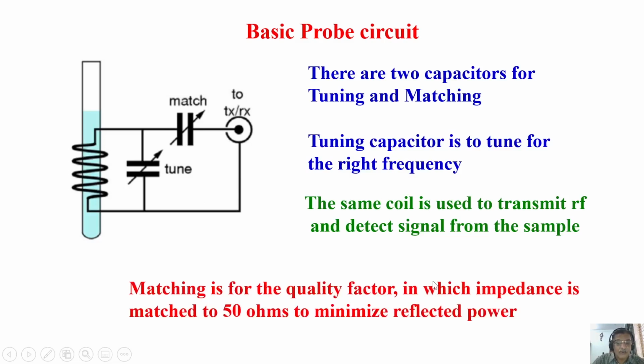Okay. And how do you match the impedance? There are two types of impedance matching which you know in basic electricals. One is 50 ohms matching or 75 ohms impedance matching. I think most of the spectrometers use 50 ohms impedance matching. So this capacitor is tuned to match the transmitter and receiver impedance. This is tuned to match the input frequency and the probe frequency for the nuclei of our interest. And this is where the sample is put. This is the RF coil. Very simple, right? Very simple circuit.